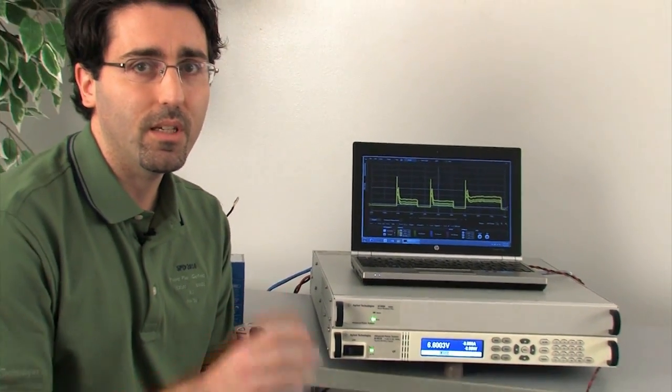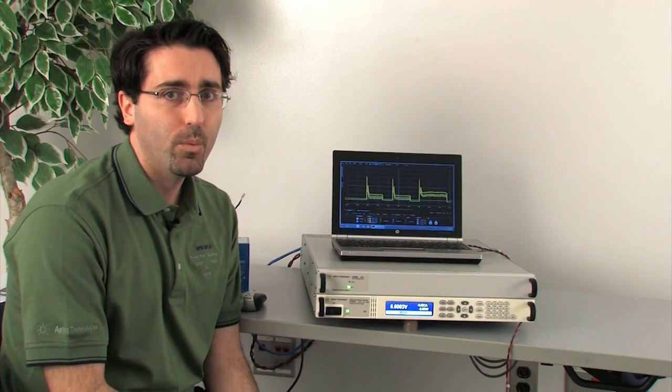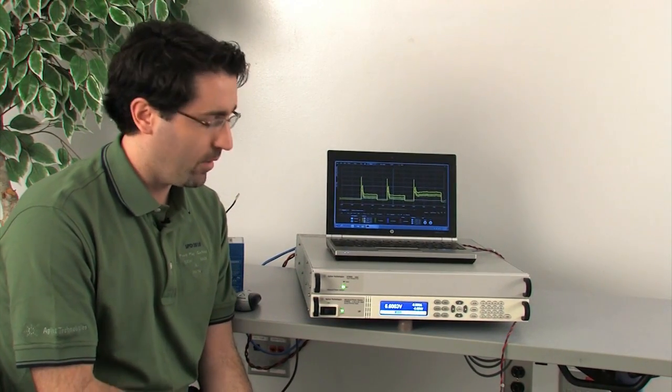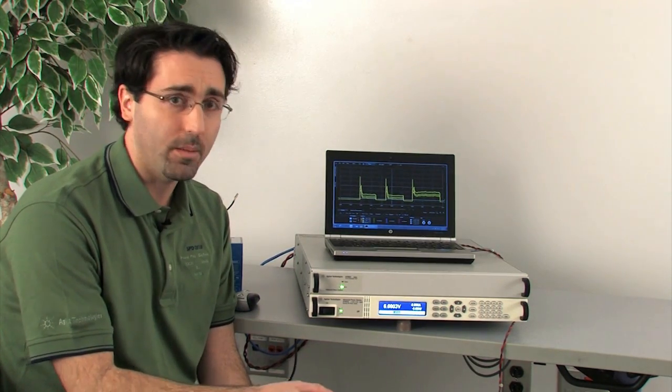But if we want to take a closer look at the power consumption, we can use the 14585 software. The power supply, the N7900, has a built-in digitizer and we can use the software to actually look at that data and what the waveform that the motor is pulling from the power source looks like. So let's take a look at the software and what that waveform looks like now.